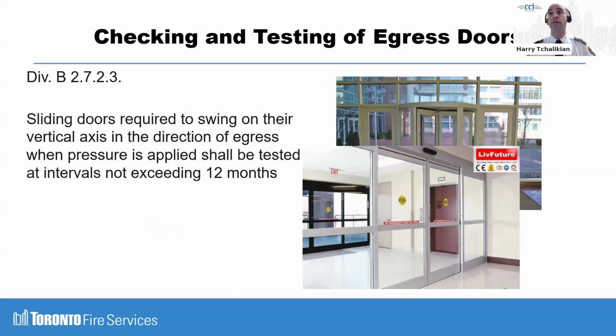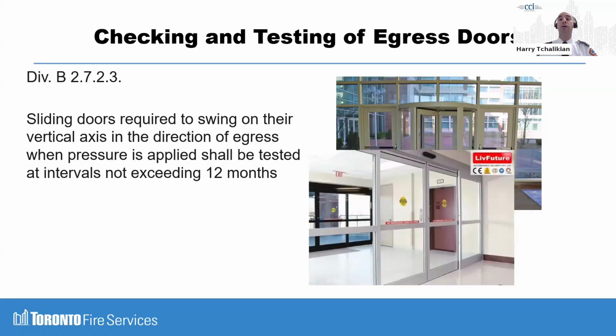Next, sliding doors. Sliding doors required to swing on their vertical axis in the direction of egress when pressure is applied shall be tested at intervals not exceeding 12 months. And so that's for your sliding egress doors. It's supposed to push open in an emergency if it's along a means of egress. So you just have to simply test that feature with a normal amount of force, which has always been 90 newtons, Newton being the metric system unit of force. Does the door open? Very good. Check. That's it. Just a checkbox on your annual record keeping.